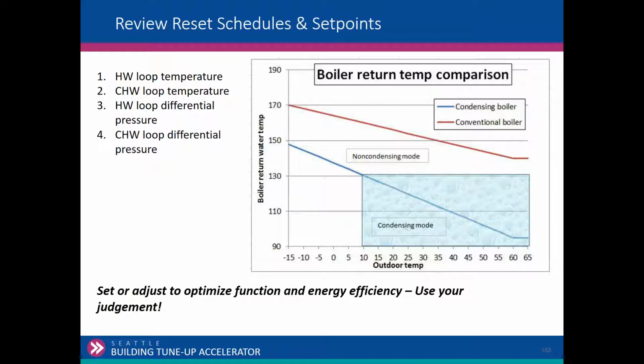Boiler loop temperature, saving on distribution energy costs. And obviously you're going to need to use your knowledge there. If somebody's running their boiler at 180 degrees and you tell them to drop it to 150 degrees, you better make sure what kind of boiler they have. So we know from experience that condensing boilers can be reset to much lower temperature than non-condensing boilers. And so you're going to have to use your judgment on what's the appropriate resets for these boiler conditions and what kind of system they're running on their hot water loop temperature, chilled water loops, differential pressure. So we're looking at you to apply what makes sense in this application. Use your judgment.